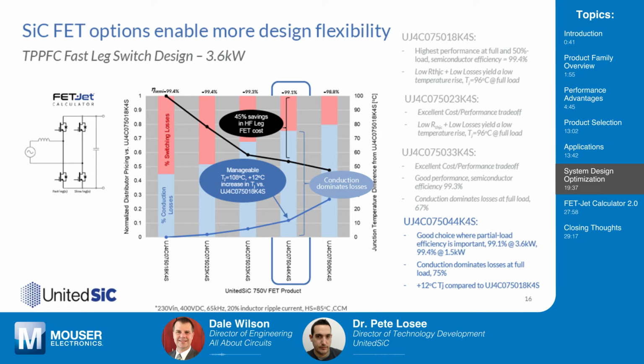It was a good way to look at it. Someone may look at the top of those and think, well, 99.1 to 99.4% efficiency, or even from the far right, 98.8, all seems so high that who cares? But if we flip it and look at the losses, you're talking about a 2x range in the losses. So it's significant, really, in the long term.